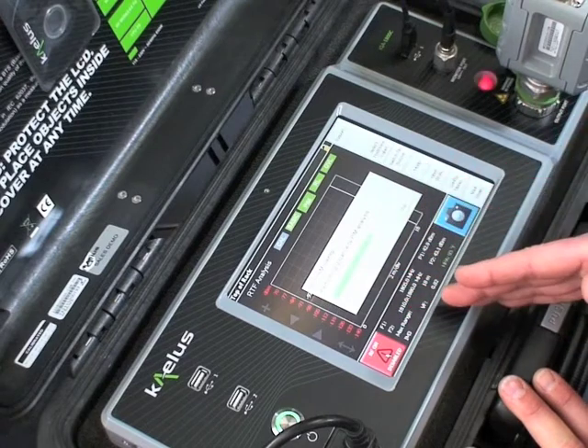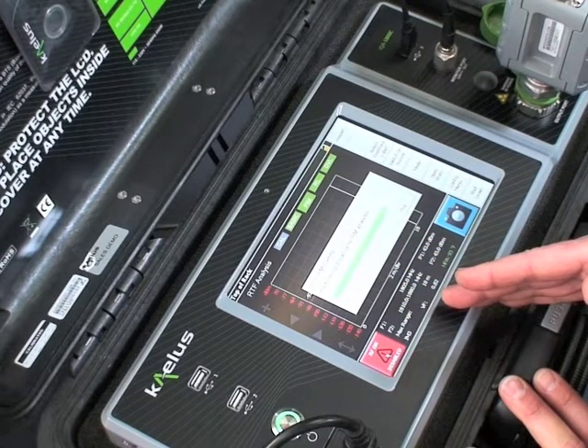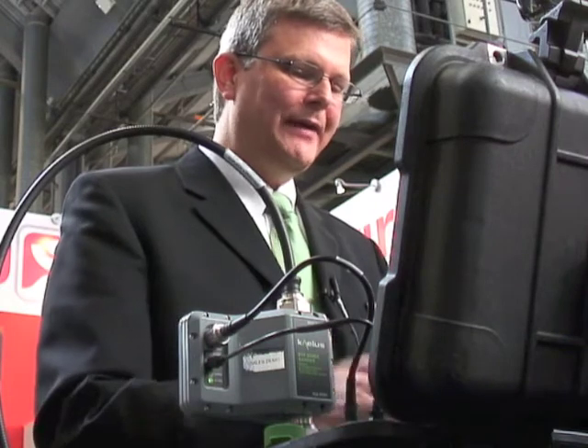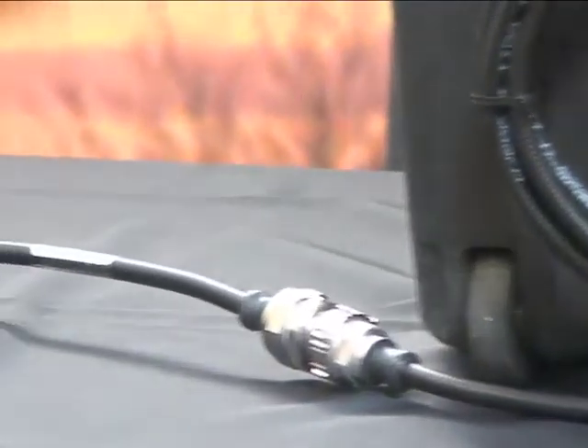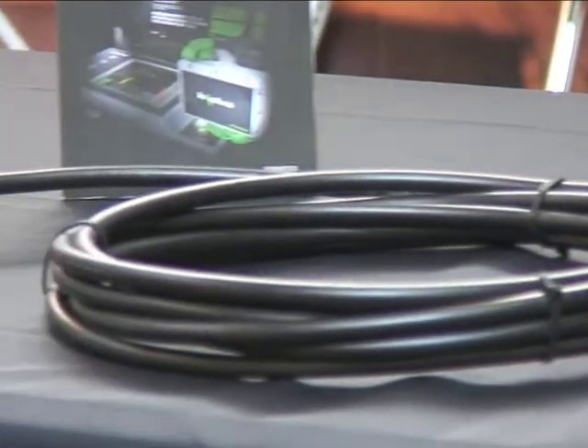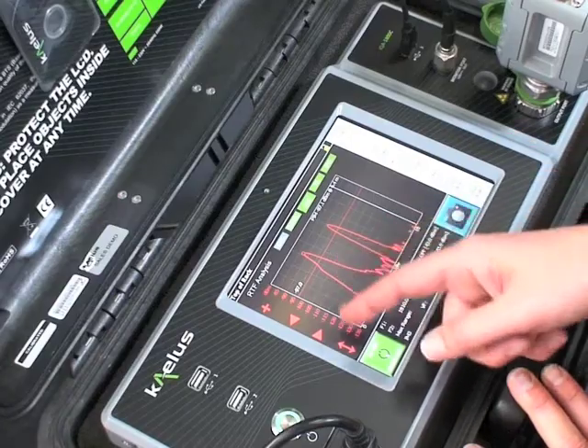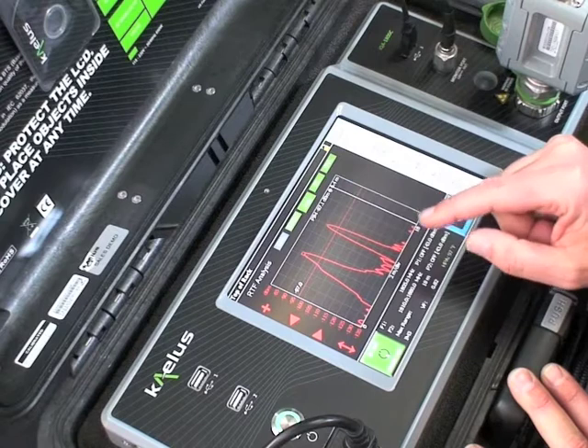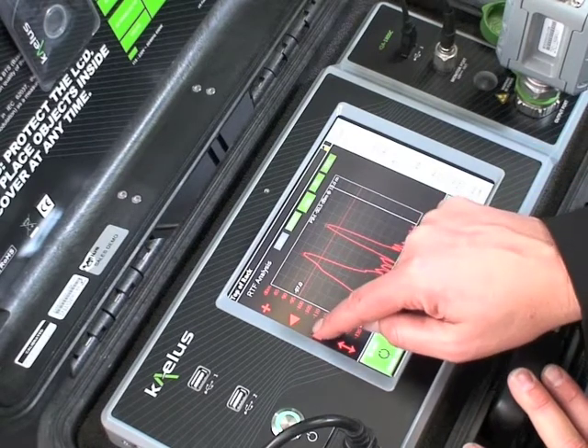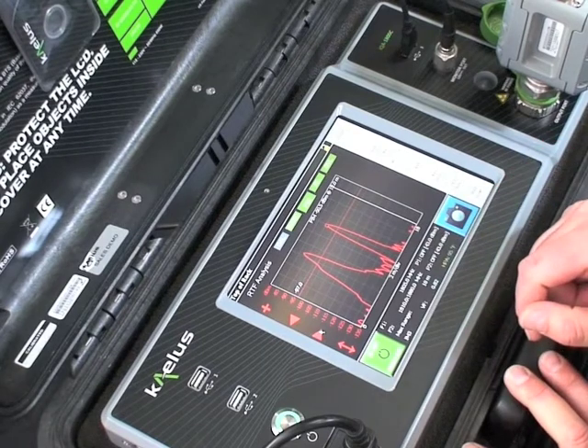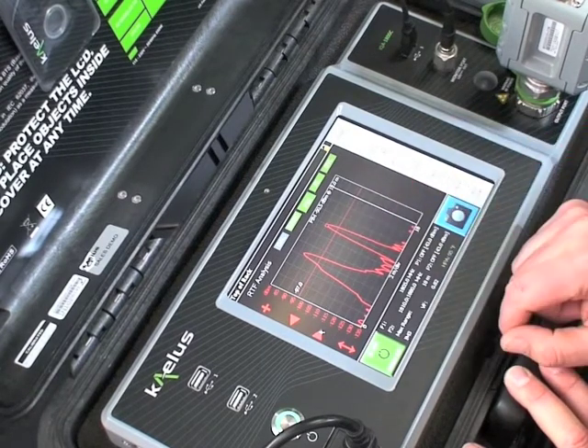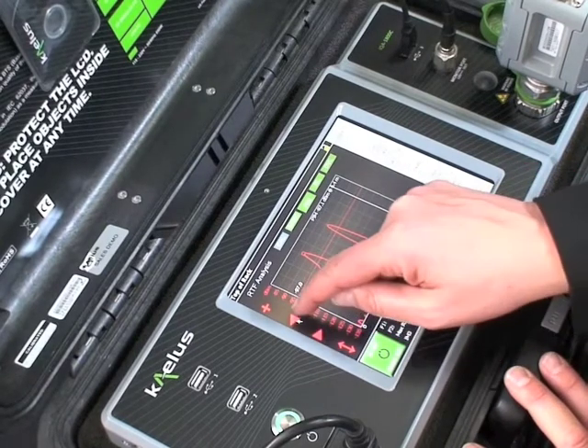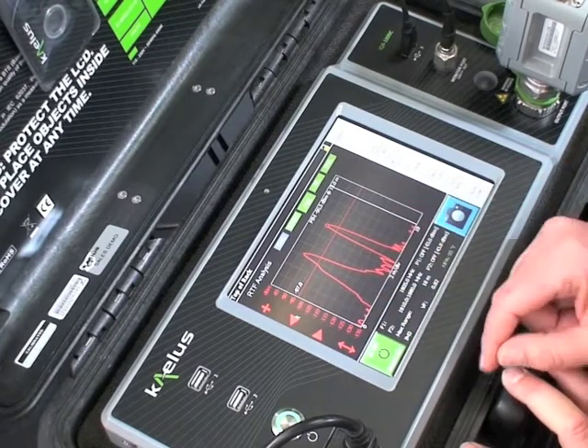I now go into the RTF sweep, which is the passive intermodulation sweep, and the analysis is complete. On the system we have set up here, we have six meters of cable, a PIM fault, another six meters of cable, and another PIM fault. The first peak is showing at a distance of 6.4 meters at a magnitude of minus 87 dBm. Toggling to the next one, another PIM source measuring minus 90 dBm at a distance of 12 meters. For accuracy: a known location of 6 meters measured 6.4 meters, and a known location of 12 meters measured exactly 12 meters.